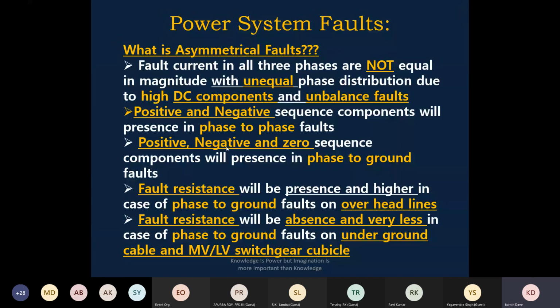Normally, positive and negative sequence components will be significantly high in a phase-to-phase fault, and positive, negative, and zero sequence components will be significantly high in a phase-to-ground fault. Phase-to-phase fault में zero sequence component वहाँ पे नहीं मिलेगा. Fault resistance will be present and higher in case of phase-to-ground fault.